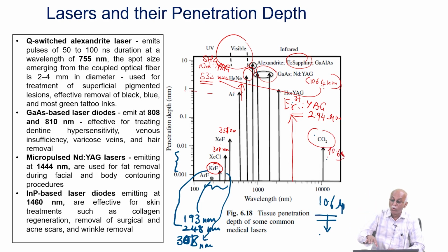Previously, before Nd:YAG lasers came into the picture, in the 1990s the CO2 laser was used to correct the tissue structure whenever there were retinal pathological conditions. But in order to use the CO2 laser, you would have to remove the cornea and the lens, and only then would light propagate through. Otherwise the lens will absorb 10.6 micrometer wavelength light and it will be damaged.